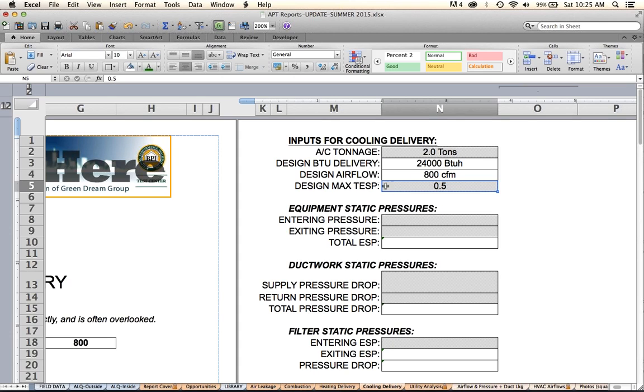Maximum design total external static pressure. And if you don't know what static pressure is, I'm sorry for the next half an hour, because none of the rest of this is going to make too much sense for you. But review it when I make the video for you. The total external static pressure in my book is 2.3 or 2.2 or something like that. Anyway, most of the time it's half an inch of water column. If it's different in your particular case, feel free to put, you know, 0.8 or 0.6 or whatever it is that you find. And this is always on the equipment label.